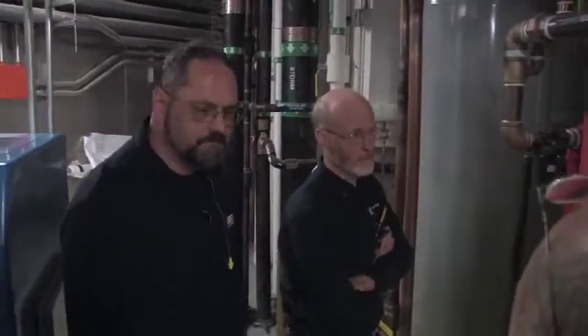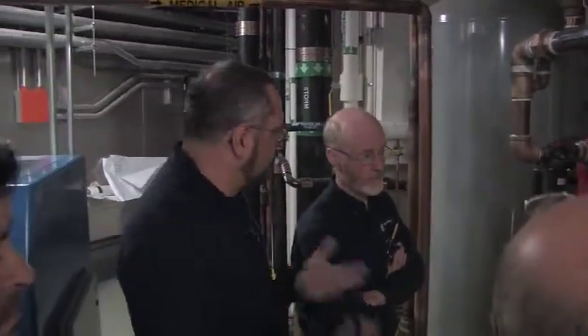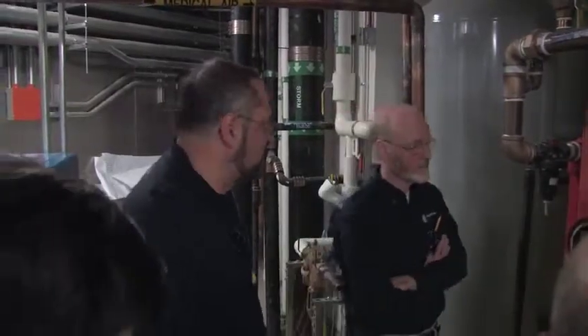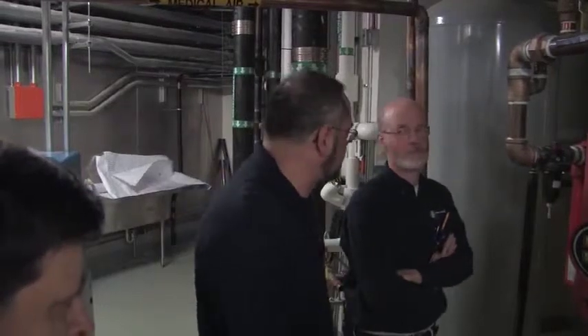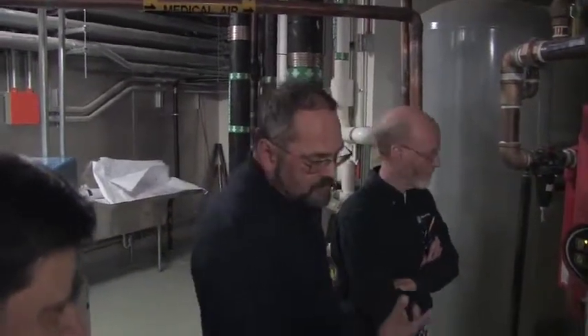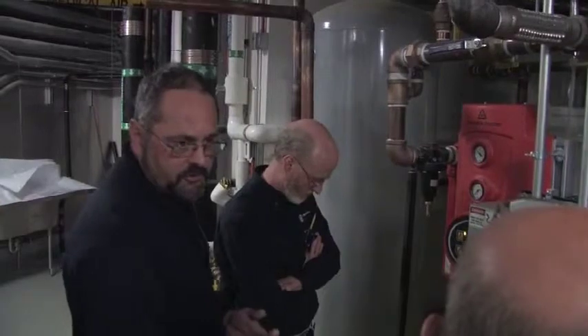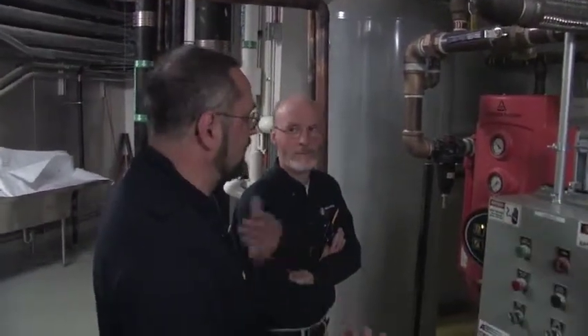Now that being said, if the gauge hasn't moved and you take it out and you blow it clean and very little dust comes out, sometimes you leave it till the next time. But again, if you're trying for no downtime, total preventive, you're better off to change the filters and the mufflers once a year. Now rebuilding the solenoid valves that do all the actuation and the check valves internally is something you do every 2 or 3 years. Roughly, usually you figure about every 3 years. And that coincides normally with a 3-year desiccant life.